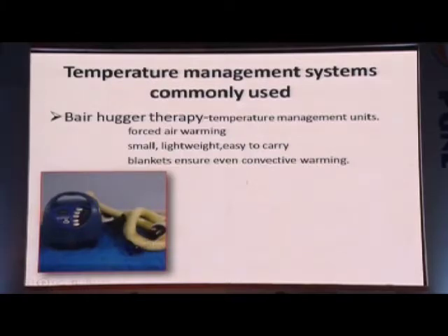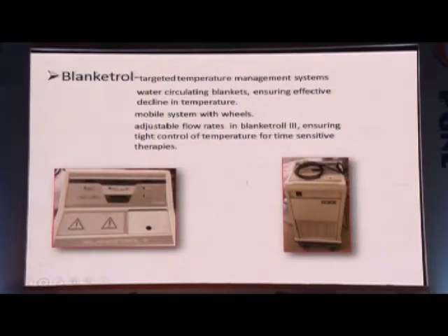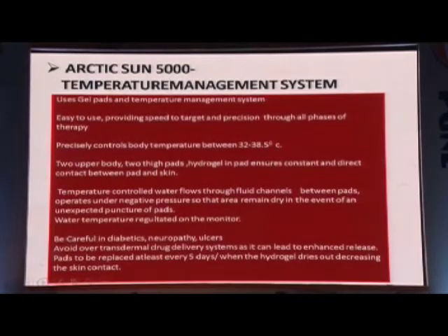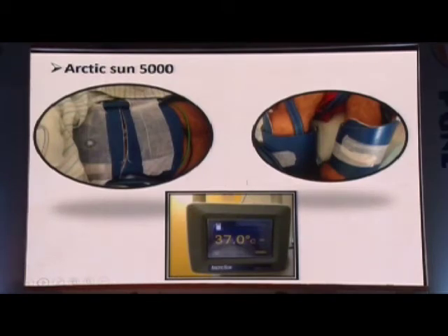Different methods for warming or cooling the patient: the Bair Hugger is a forced air warming device which most of us use — easy to carry, can even be used in an ambulance. Blanketrol is the traditional hypothermia blanket used under the patient during CPB surgery. Different types of blood warmers should also be used, particularly in off-pump CABG patients who tend to get hypothermic — if you want to extubate them earlier, it is important to maintain temperature. Arctic Sun is another temperature management system using gel pads on the patient, which cools much more effectively than other methods, typically for 24 to 48 hours.